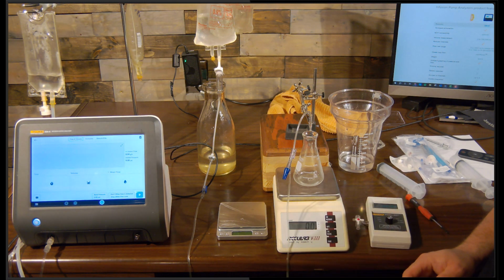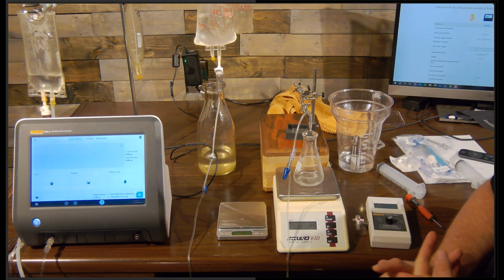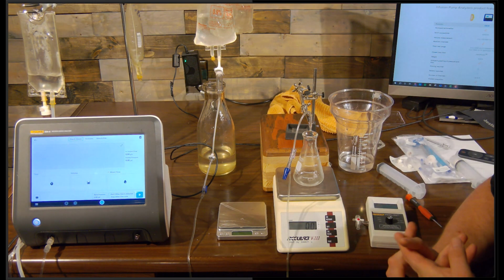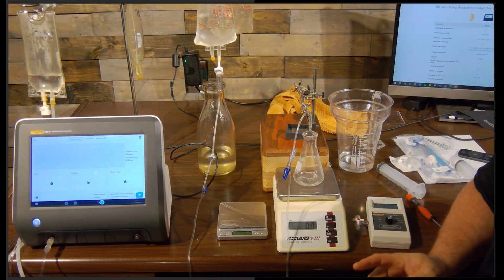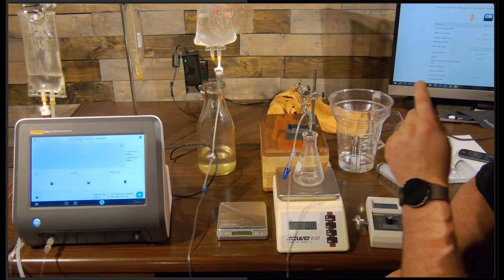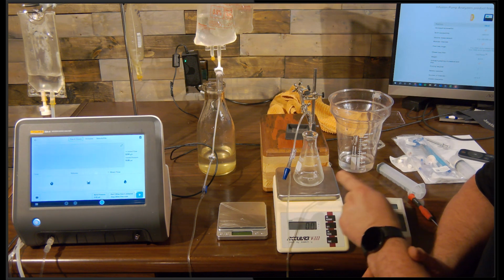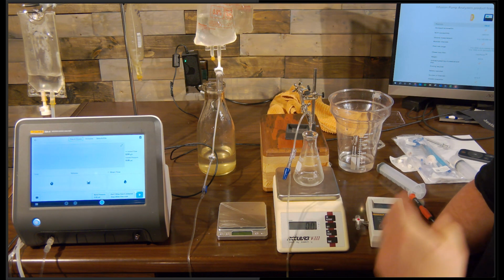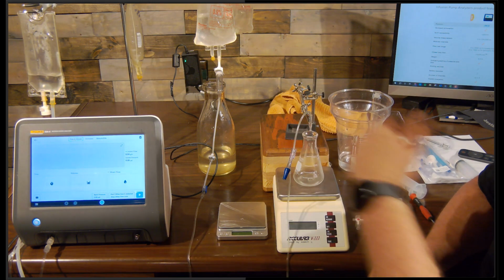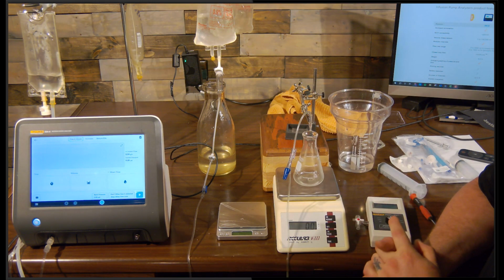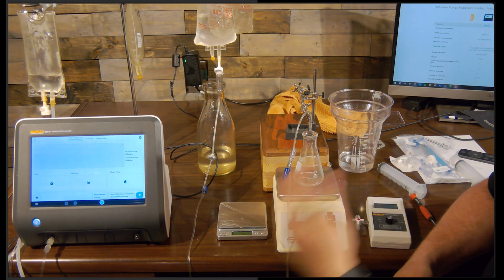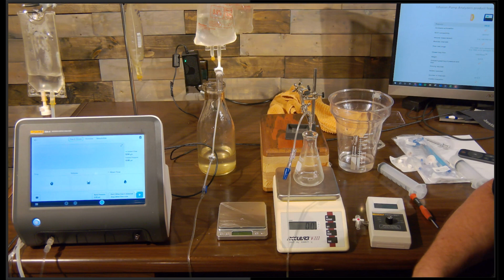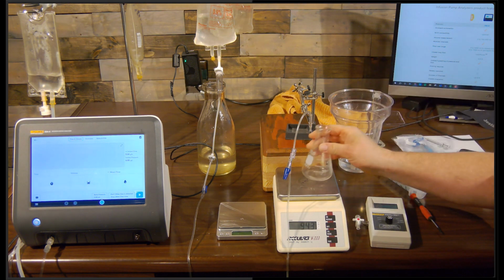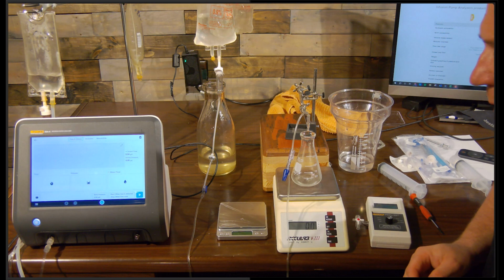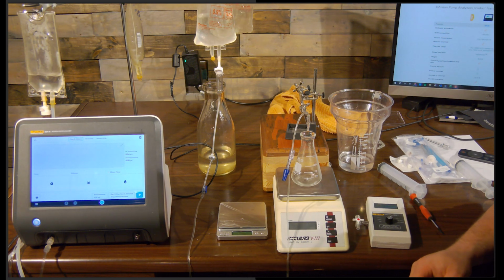So if I got distracted, say my phone rang, or somebody walked into the biomed shop and asked a question, or I had an email pop up that I had to take care of, and this used to happen to me a lot when I was a field tech, I would get distracted and not catch the end of the test. And then I had to guess, well, how long did it sit there from the time it beeped to when I read it? Is a little bit of KVO enough to throw off my measurements or not? It calls a lot of things into question and can add some uncertainty to your tests. And then I had to dump it back out and start over again, and I'd always end up repeating 2 or 3 tests a day because I got distracted, and that's more time on a good day. Some days the phone rang a lot.